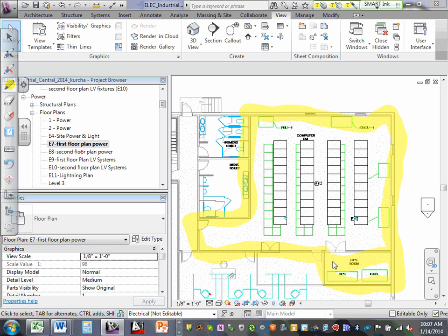Yeah, but before we leave, this is where the UPS area is. Would you apply the same rule to the UPS area? Usually you do not have pre-action in the UPS room, but we sure could. I would say in the UPS room that you aren't going to have all that air movement, so you could go with your standard 30 foot by 30 foot spacing in the ceiling.